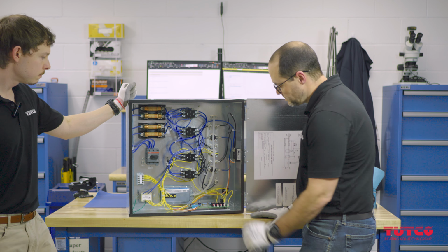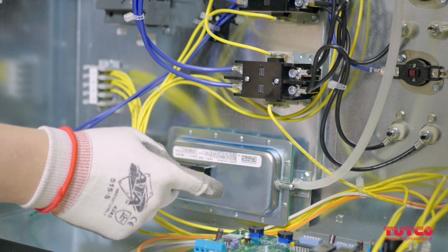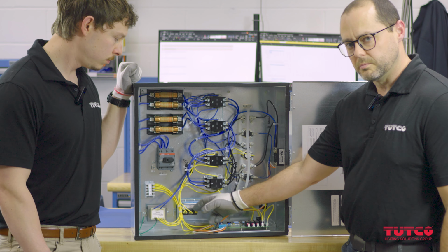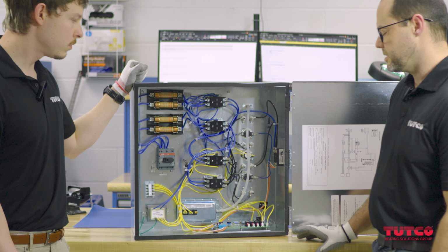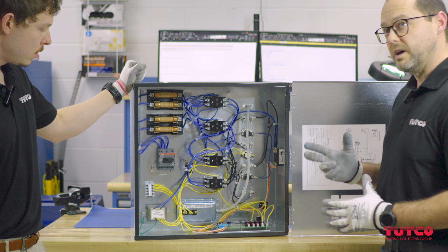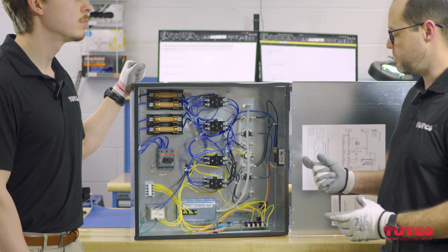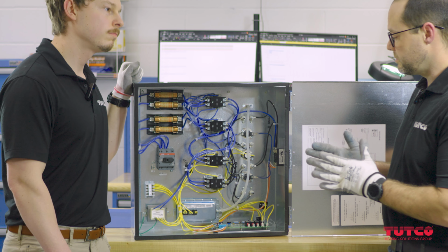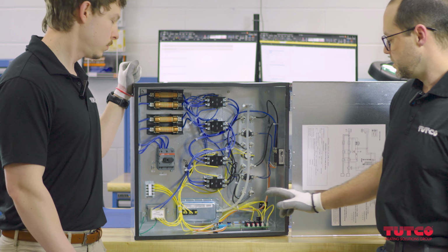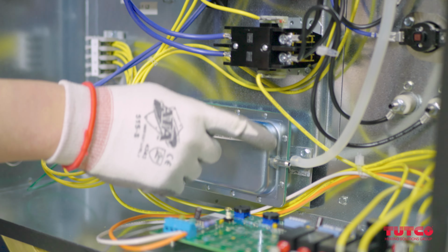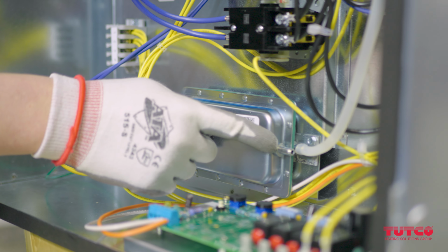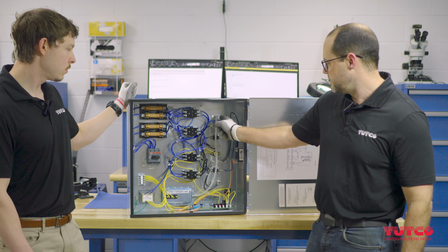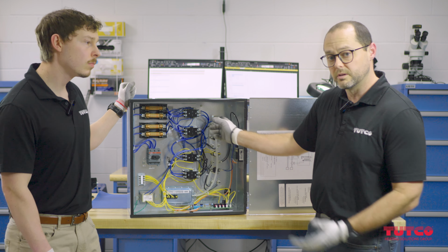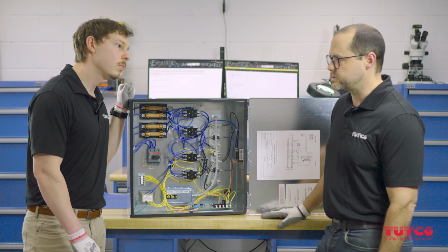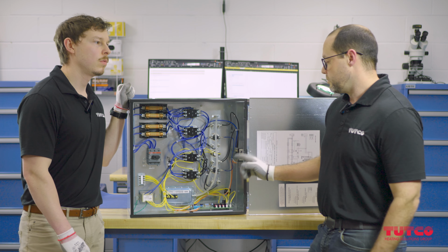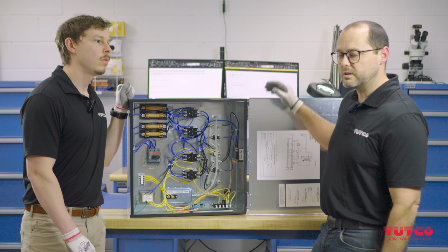SCR control. Airflow switch works with differential pressure, so it's a big diaphragm inside this box you see there. Gotcha. And if it has 0.05 inches of water column, that's the minimum set point, it can make the switch. So it uses 2 ports to determine that. So one will be open to atmosphere on this heater. The other one will be measuring the pressure in the duct. And that's how it would gain the differential pressure. So it only operates whenever the fan is running and there's a positive pressure in the duct.